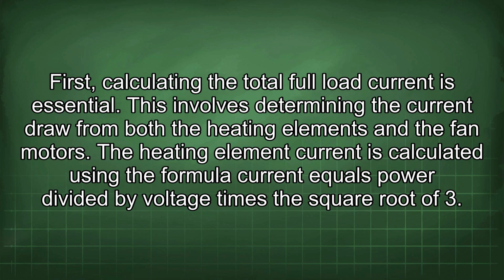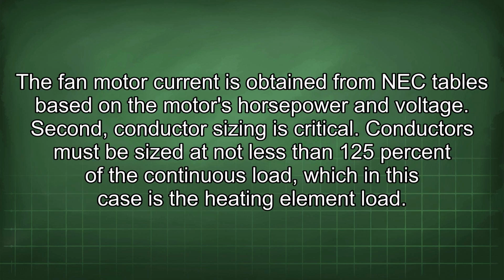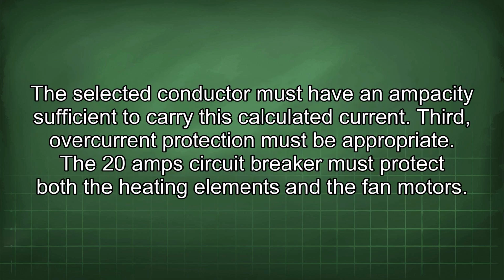The heating element current is calculated using the formula current equals power divided by voltage times the square root of 3. The fan motor current is obtained from NEC tables based on the motor's horsepower and voltage. Second, conductor sizing is critical. Conductors must be sized at not less than 125% of the continuous load, which in this case is the heating element load. The selected conductor must have an ampacity sufficient to carry this calculated current.